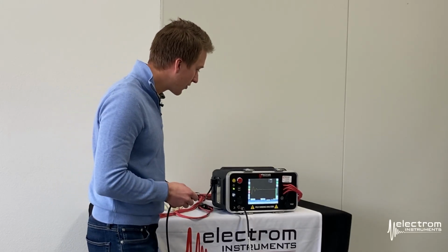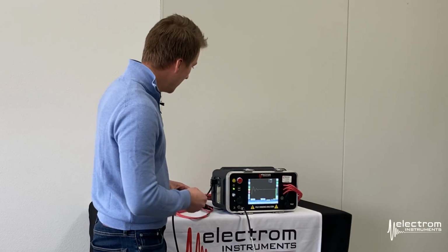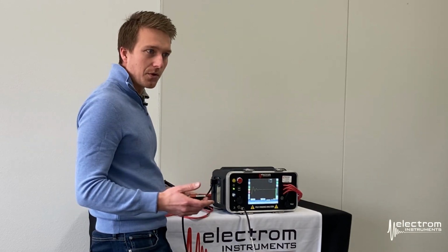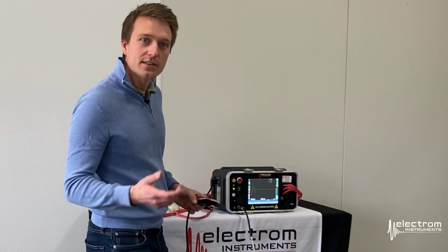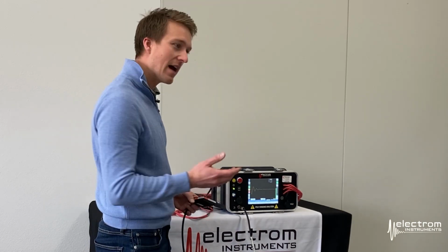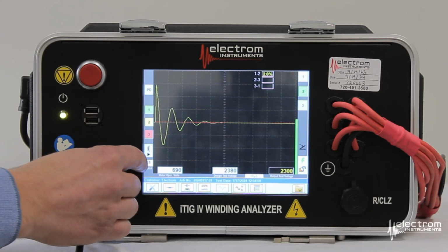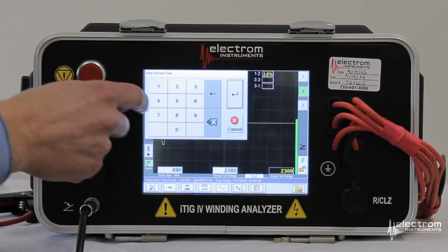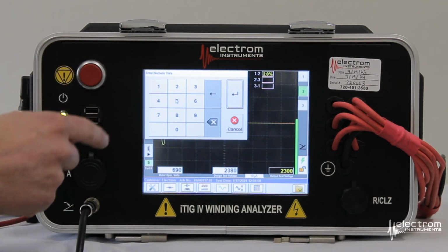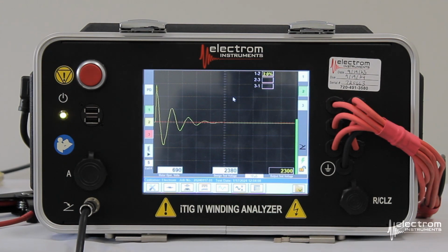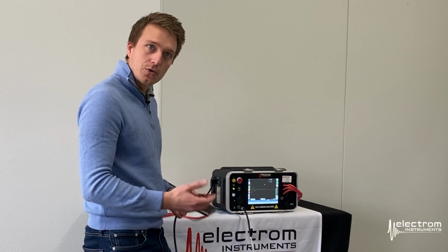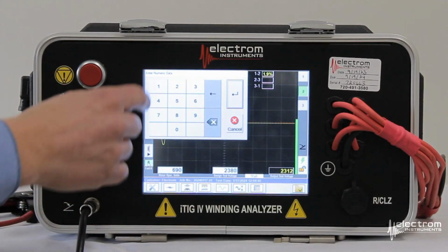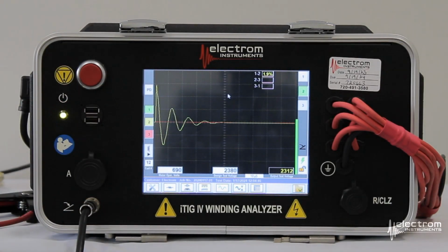One thing we want to show before we do that is in the event that you made a misconnection, or you tested a coil twice, or you did something else wrong and you want to go back and repeat a test, you can always click the field that lists the coil number and say, okay, I want to actually retest coil number 5. So enter 5, hit enter here, and then repeat the test. Great, so now you've repeated the test on coil number 5. You can go back and say, okay, I want to pick up where I left off on coil number 12. Continue on with your testing.